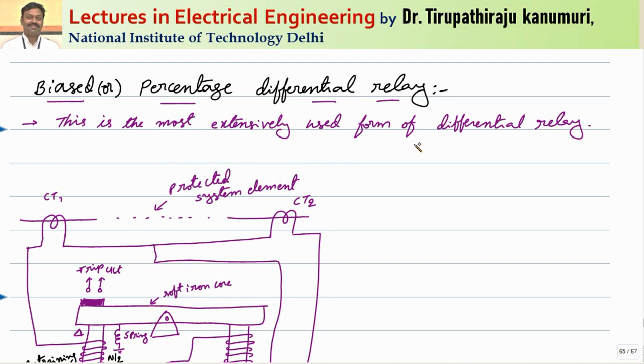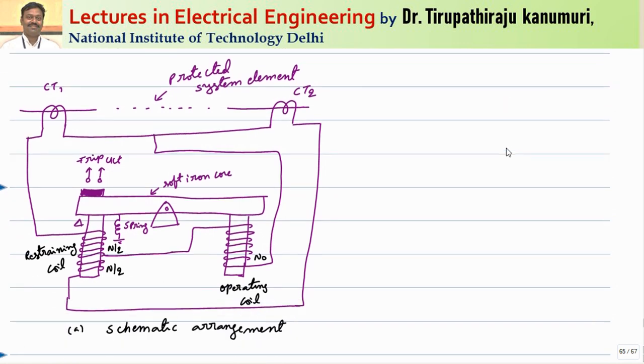This is the most extensively used form of differential relay. Let us see the basic construction. This is a schematic arrangement for the balanced beam type. The beam is balanced and it has two coils — one is the operating coil and the other is the restraining coil. The restraining coil produces the restraining force.